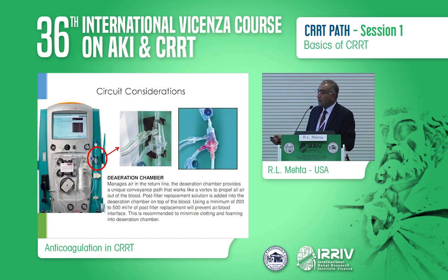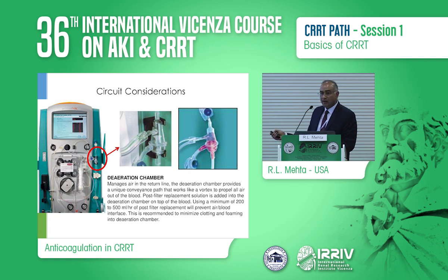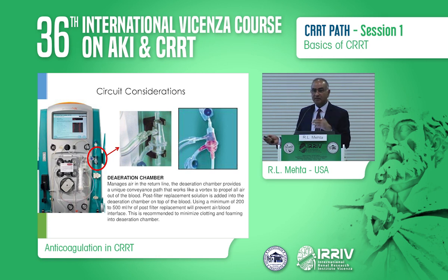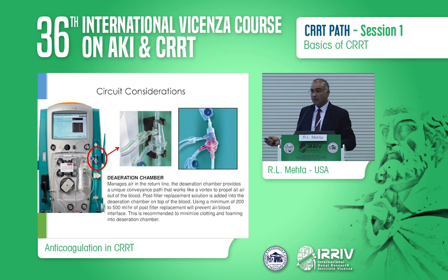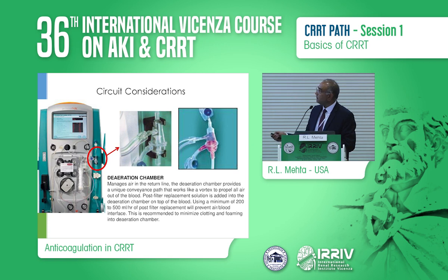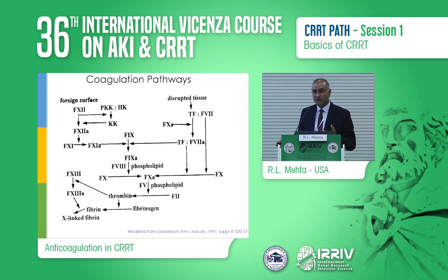The other aspect in the circuit — at least in the PrismaFlex, and I believe the same in almost all machines — is the de-aeration chamber, where you have a blood-air interface. The blood-air interface is where blood is really stagnant. This is designed so that you do not get air embolism, because you can decompress it. In order to keep this part open, you need to constantly infuse fluid post-filter to maintain the de-aeration chamber open.